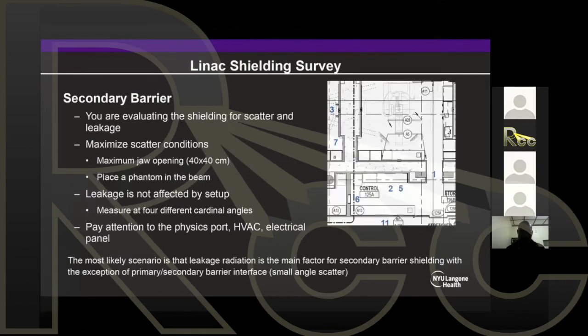So now we're gonna look at the setup for the secondary barrier. So here you are now, so imagine we're in the control room, right? You're evaluating the shielding for scattering and leakage. The beam, this gantry, is never gonna be pointing against this wall. So you're gonna maximize scatter conditions. So you're gonna open your jaws, you're gonna place a phantom in the beam, you can just use your water phantom. Leakage is not that much affected by setup, so you can just leave that for the leakage as well.